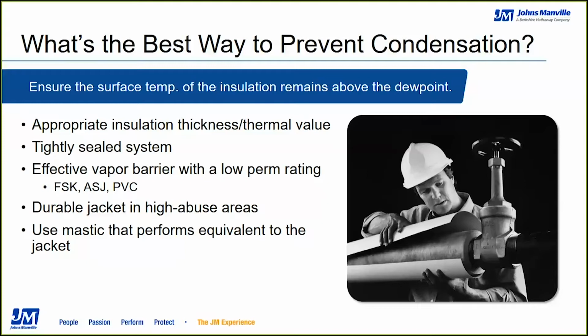And then PVC can be a low perm vapor barrier. And perm rating is how a vapor barrier is evaluated. Typically, you want to have a perm rating below 1, and most JM insulations have a perm rating of 0.02, so quite good at being a vapor barrier. For a high abuse area where there's an opportunity for the vapor barrier to get damaged, some sort of jacketing is recommended, like a PVC jacketing or perhaps a metal jacketing. And mastics are very often used to help seal up the system and any imperfections. And you do want a mastic that has a very good perm rating as well, at least below 1, but you can get them as low as 0.02, similar to the jacketing.